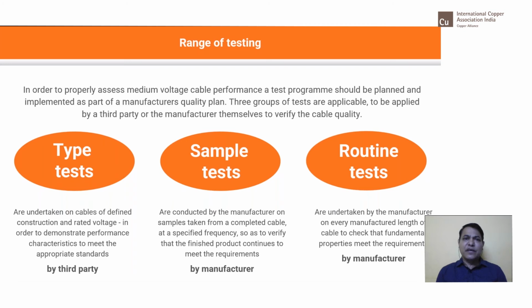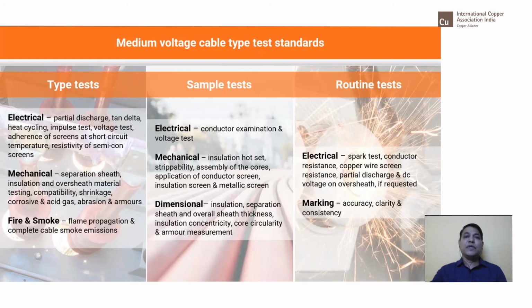The routine tests are conducted on every length of cable, on a completed cable in the manufacturing process, or during the process itself, each stage of the cable manufacturing process, from conductor to insulation, sheathing, bedding, armor, on the process also it is tested. So I will cover more on that in the next slide. This is how they look like.